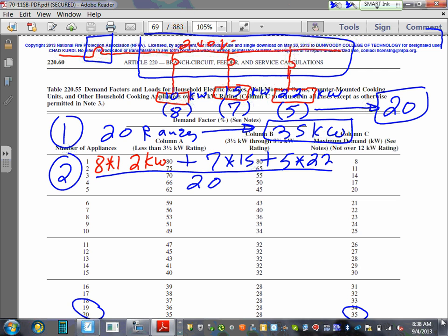One more time. The note we were looking at, note number 2, says average them. But before you average them, you have to do the following: anything less than 12, make it 12. That's where the 12 here comes from. It's the most confusing part of the whole business. So the 10 here became a 12. Why? Because anything less than 12, make it 12. That's what note number 2 says. So instead of 10, I put 12 here: 8 times 12 plus 7 times 15, 5 times 22, divided by 20.